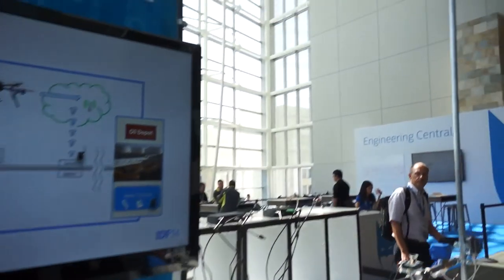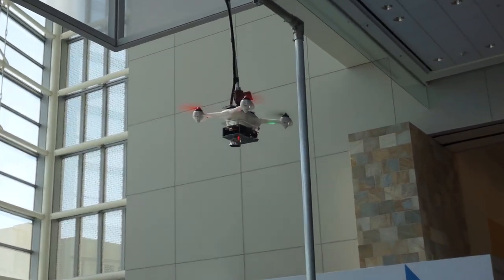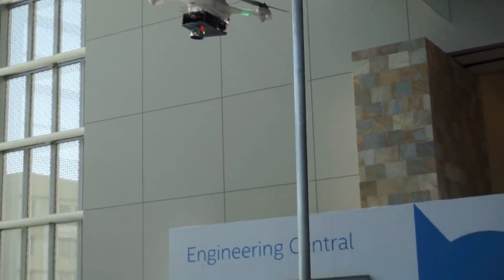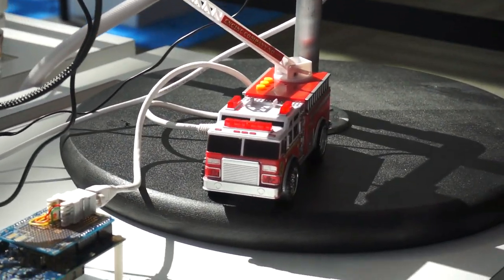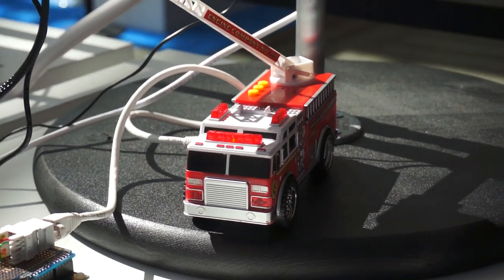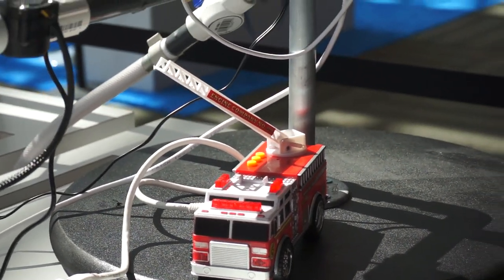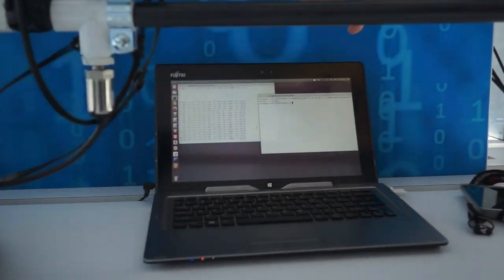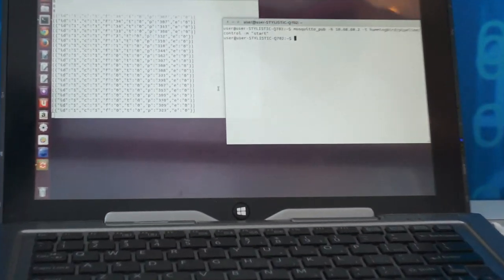I'm going to bring that data back. And then what we see here is it lit up my fire engine, started to hear some sirens. So I wired everything in here and then it shut down my pipeline and shut down all the valves. On our data that we're looking at, you can see the temperature jumped up to 728 and our flows have now dropped to zero as it shut down all the valves.